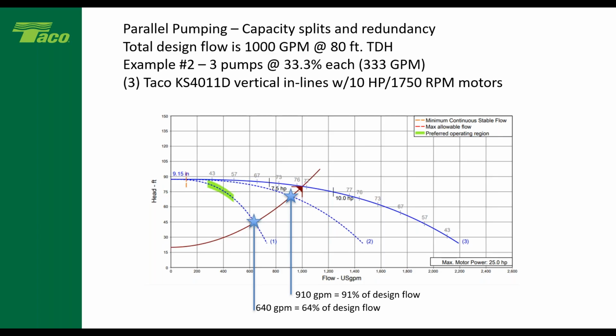So as you can see, if I go from two pumps to three pumps or even four pumps, because that MPC is capable of operating up to four pumps in parallel, I can do three pumps in parallel plus a standby, or I can do four pumps without a standby. So however you want to break it up. But the advantage you have is if I do three pumps, each sized at 33%, now if two pumps are operating, so N minus one, now I've got 91% of my design flow.